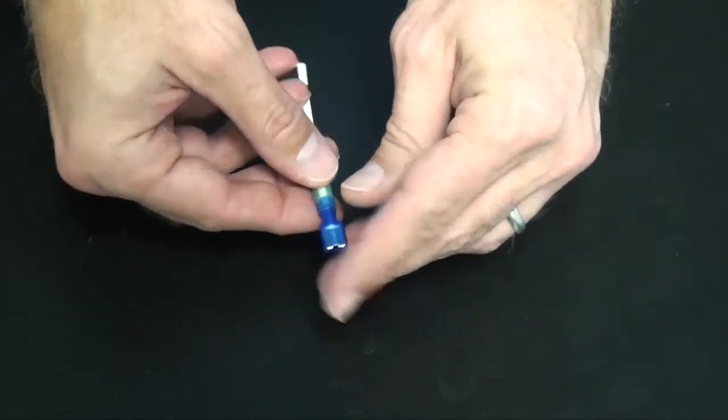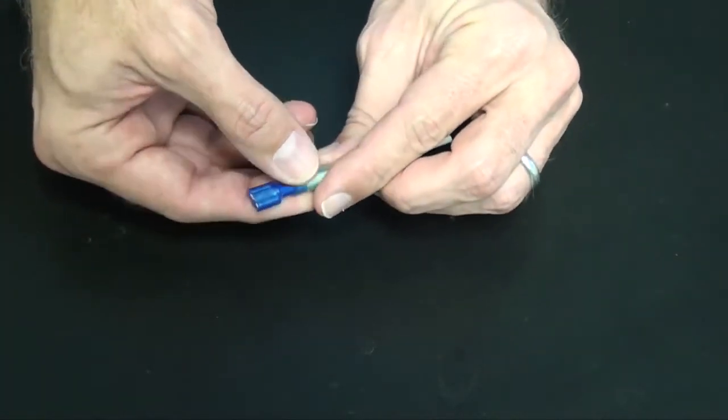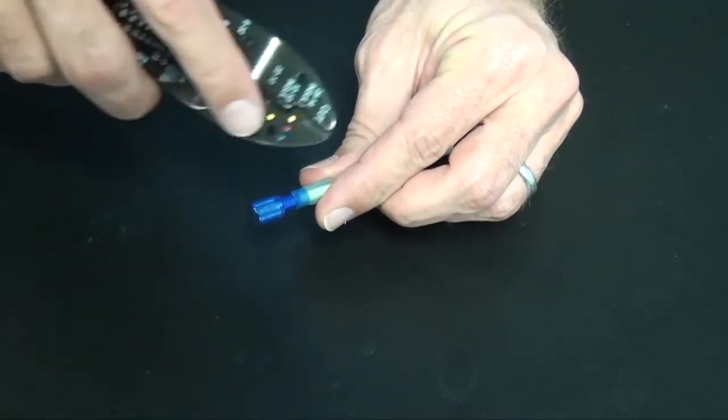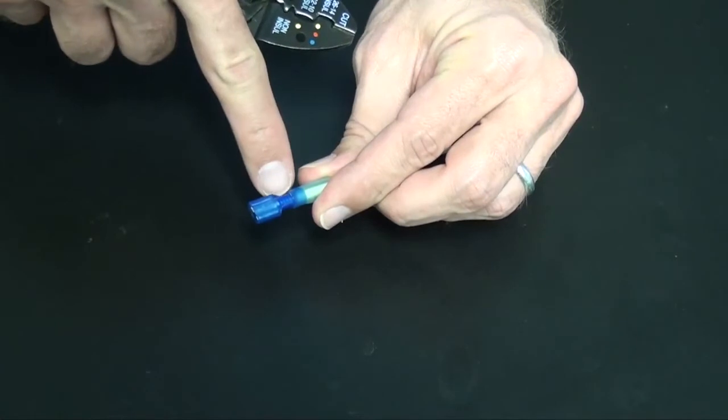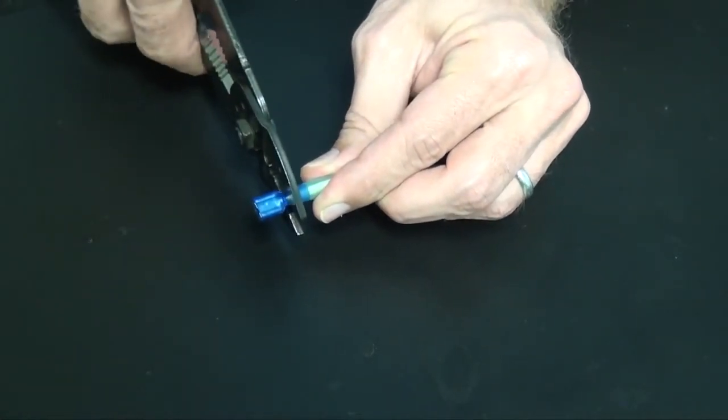Insert your wire into the barrel, making sure that the ends of your wire butt up against the terminal's wire stop. Using the blue crimp nest of your crimping tool, align the tool in the middle of the crimp area of your nylon terminal and crimp the connector's barrel.